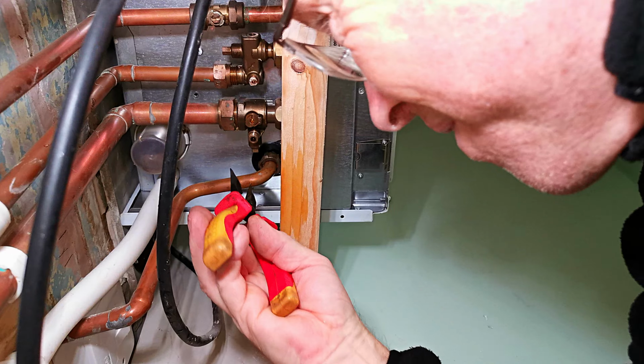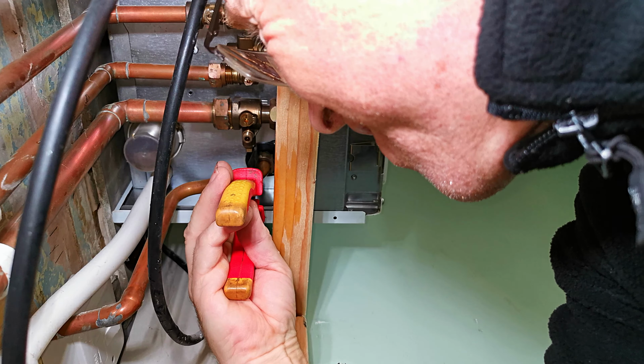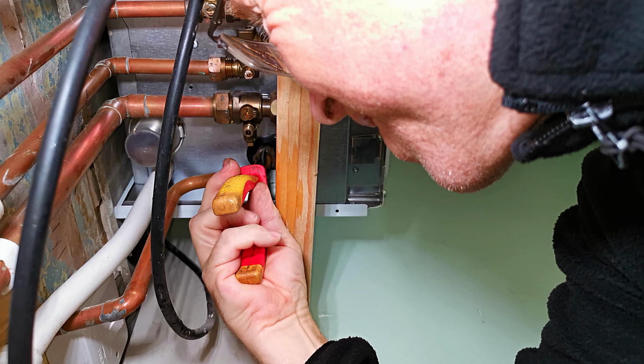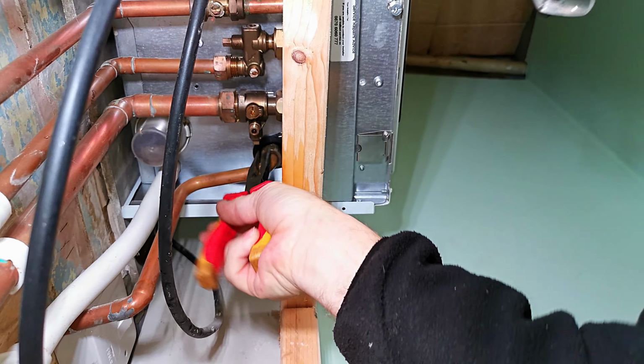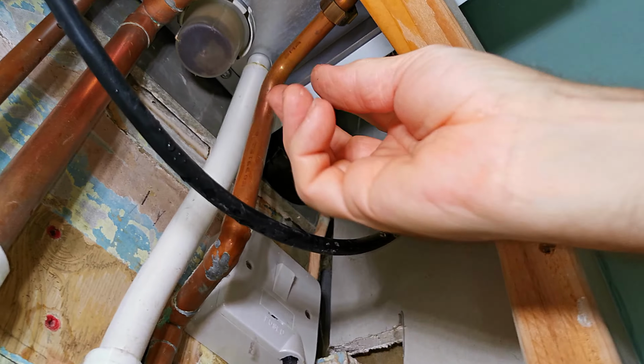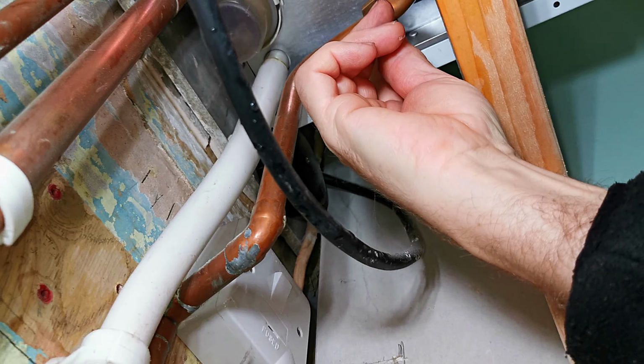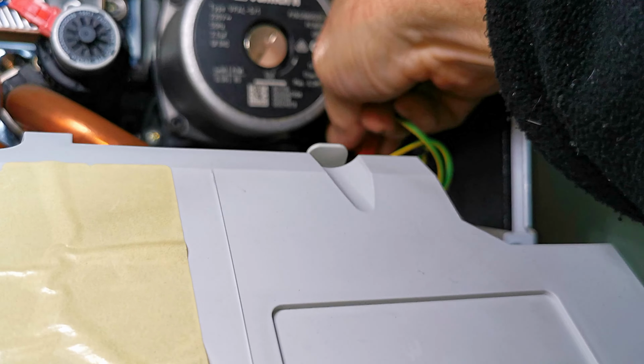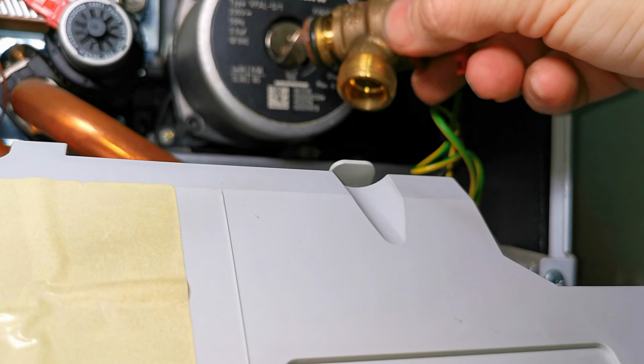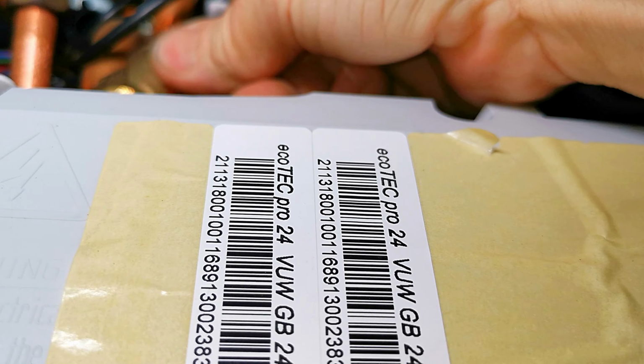I need to remove the nut on the bottom, and I use a long nose pair of pliers to grip that little awkward nut up there and give it a turn. They're usually not very tight because they're quite awkward to get to, and they do up onto a rubber washer. And there we go, that's now removed. I can now give it a wiggle and lift it out of the way. And there we go, that's the pressure relief valve.